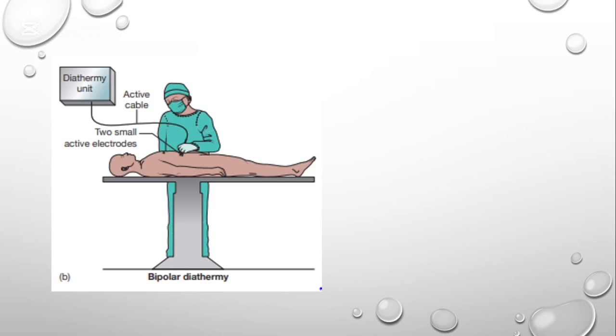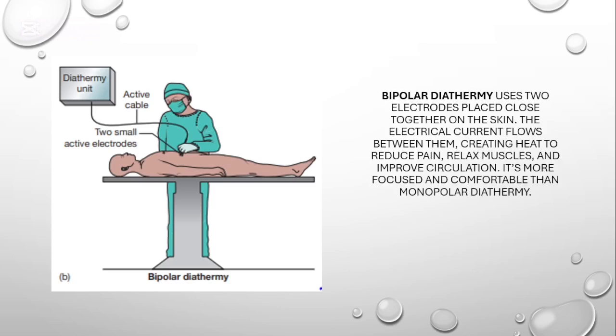Bipolar diathermy is similar to monopolar diathermy, but it uses two electrodes instead of one. These electrodes are placed on the skin close to each other. The electrical current flows between them, generating heat in the tissues. This helps reduce pain, relax muscles, and improve blood circulation. Since the current flows only between the two electrodes, it's usually more focused and less likely to cause discomfort compared to monopolar diathermy. It is commonly used in physical therapy and rehabilitation.